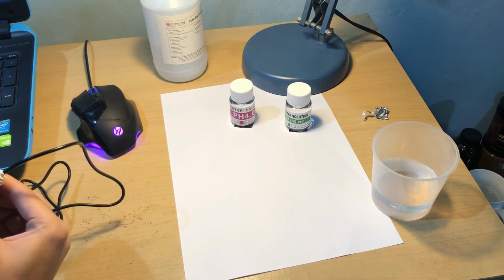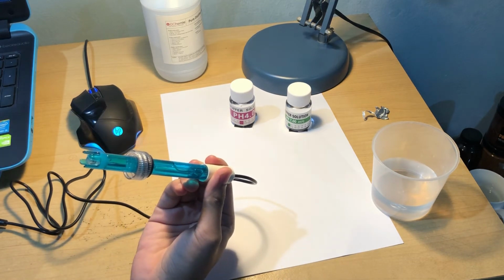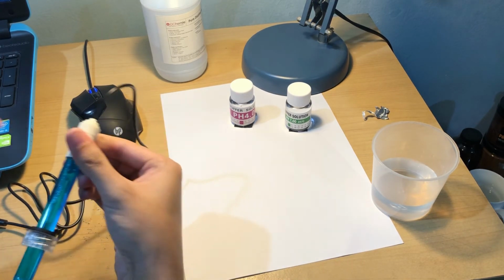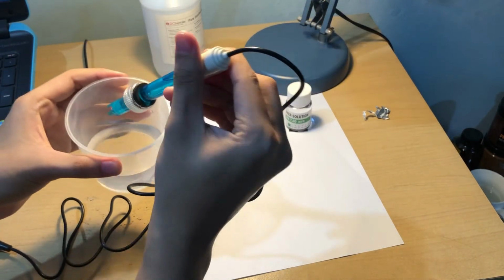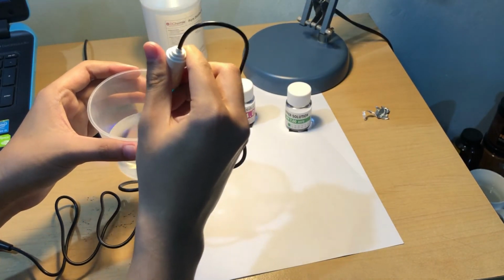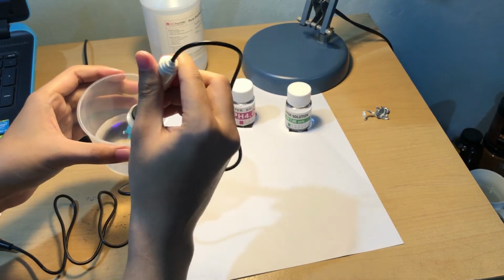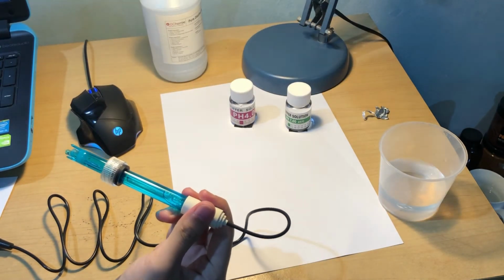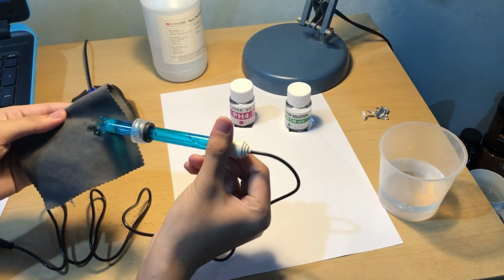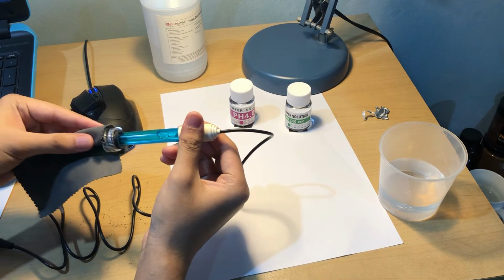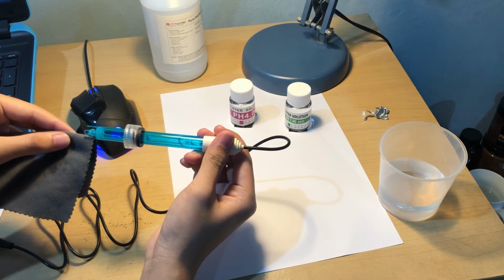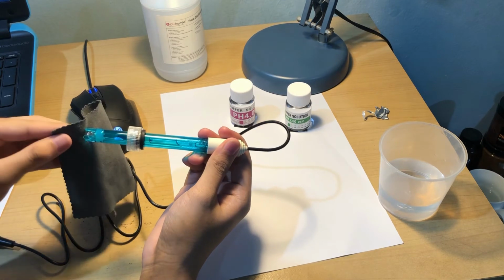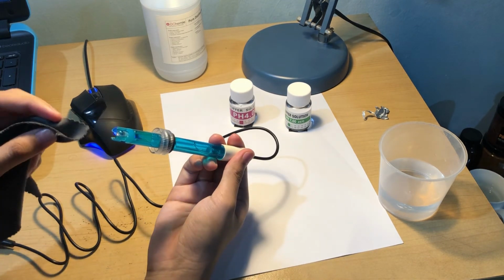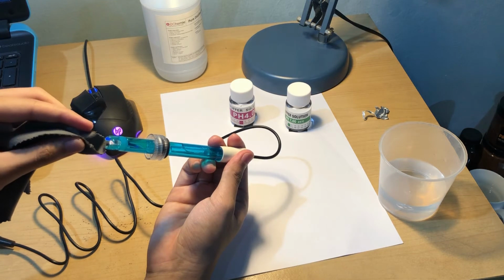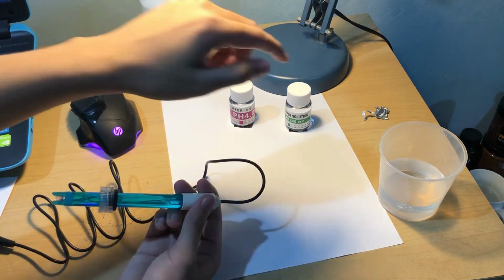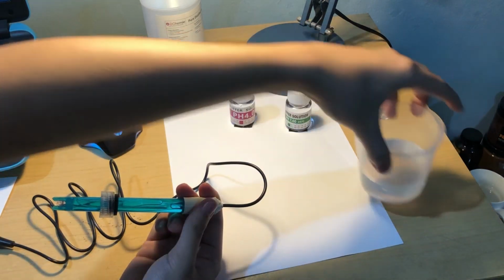So first of all, we need to open the lid of the pH sensor, and then we need to dip it into the pure distilled water just to clean it up before the calibration process. And then we need to gently dry the probe, to make sure there is no excess water. Gently clean it, dry it, okay? Be careful because the probe is quite sensitive. So now, after finishing, I will dip it in the buffer solution with pH value of 7.